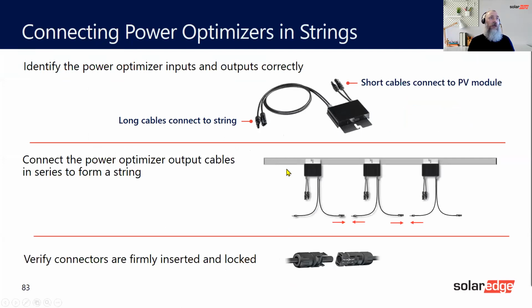As we said, the long cables, they then plug into each other because they're part of the string, and the short cables go to the module. And obviously, if you're leaving it overnight, make sure that these are plugged together. The short cables, they're for the modules, and wait for the click. Make sure that they click.